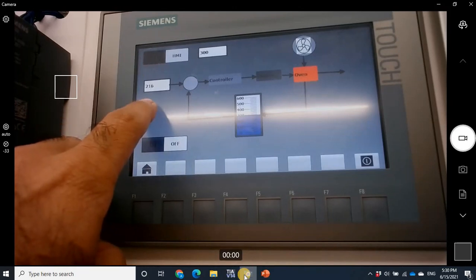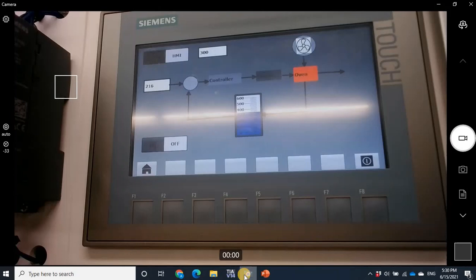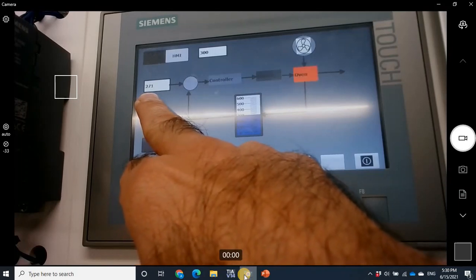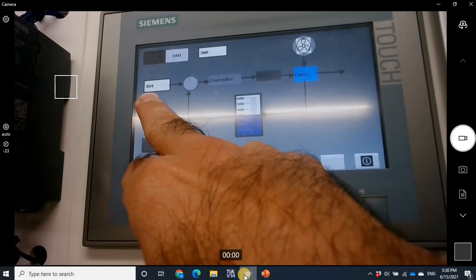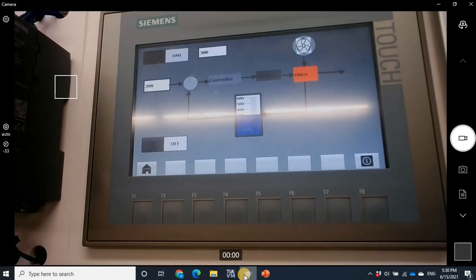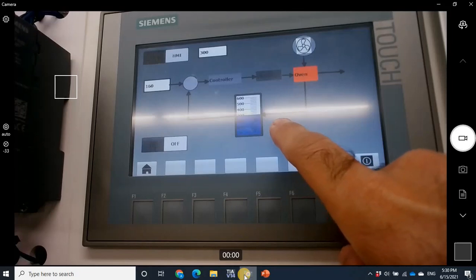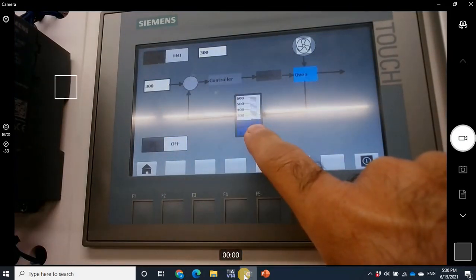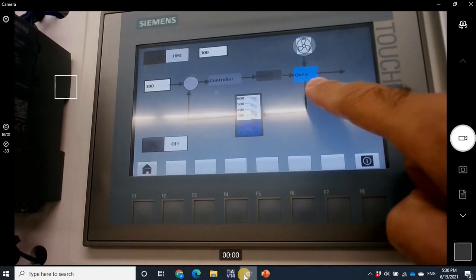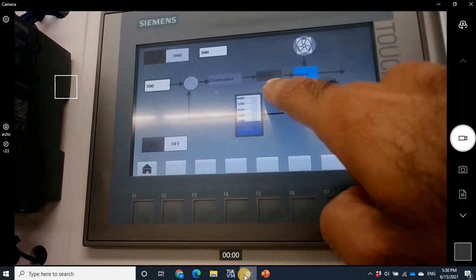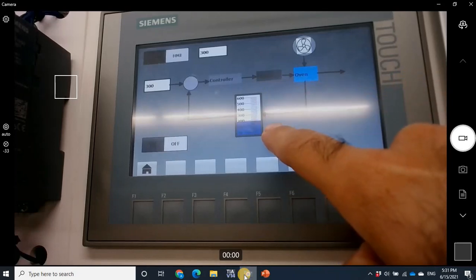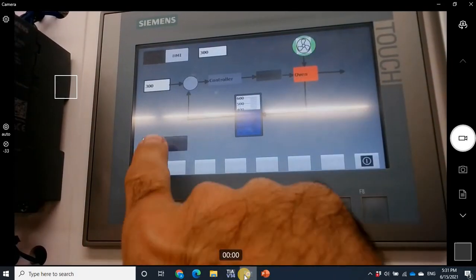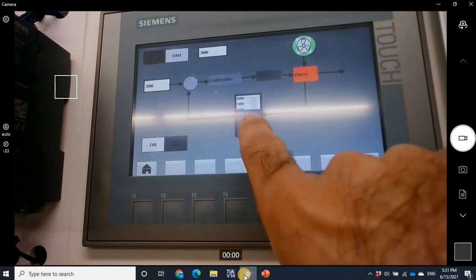Right now the set point from the external input is 260. Let's put it at 300. The oven is cold, and we expect the heater should turn on — but it doesn't. Let's look at why. The heater should turn on when the temperature is low, and turn off when the temperature is high.